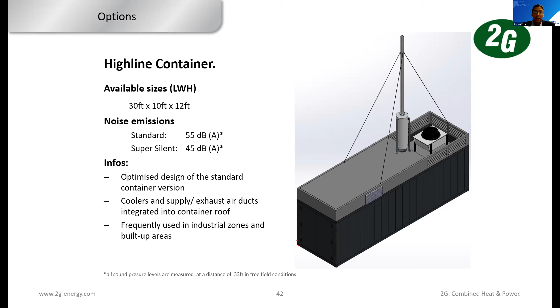The Highline Container is for the bigger engine systems: 600 kilowatts, 1 megawatt, 2 megawatt. This also has the industrial look, and at that size range you're usually an industrial customer anyway, so you could put something like this in a parking lot or company lot where there are acres and acres of space. Same as before, it's 65 decibels standard, or 55 decibels if noise is a concern, such as when you're close to the property line where the CHP container will be placed.